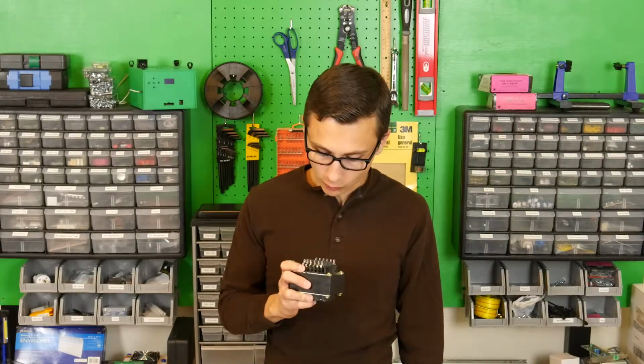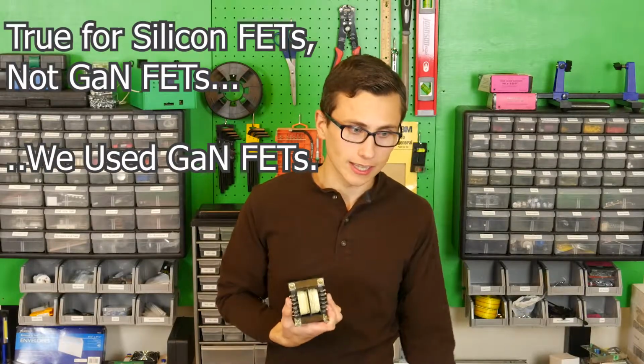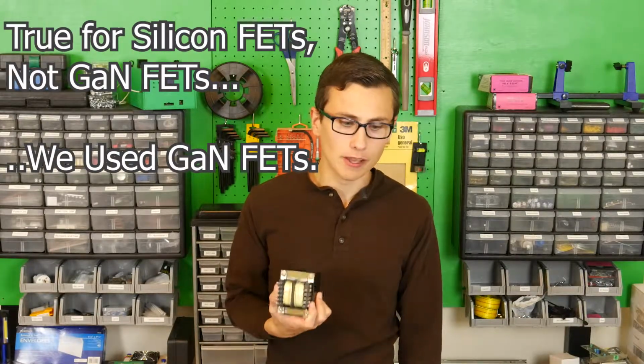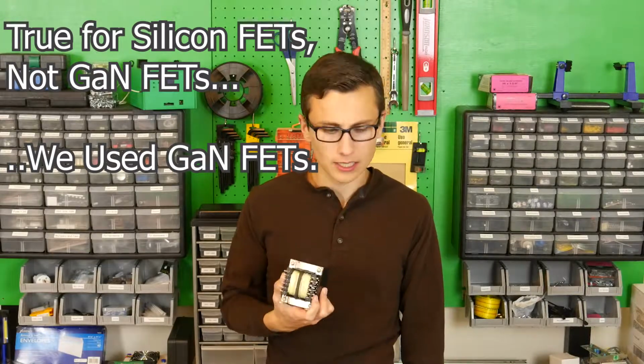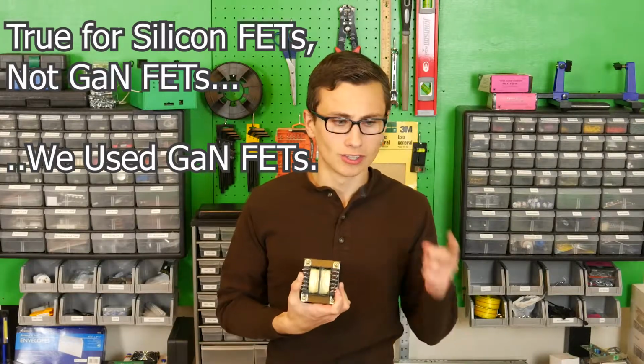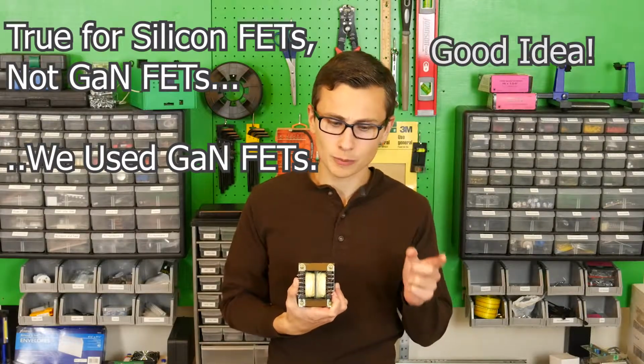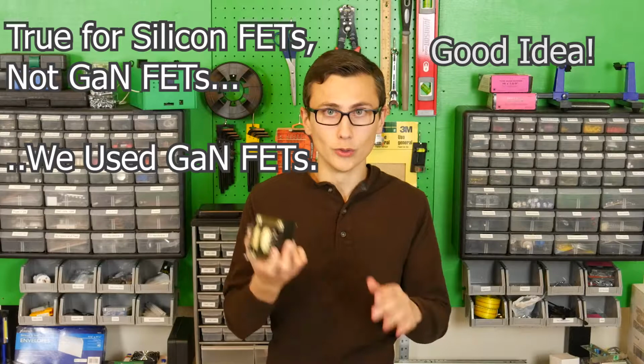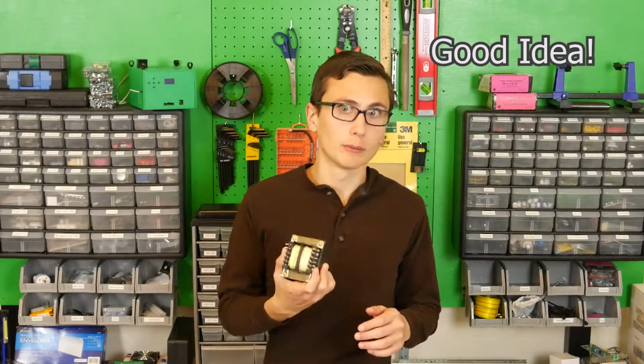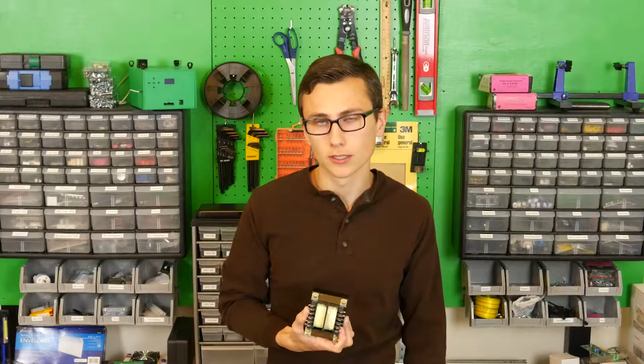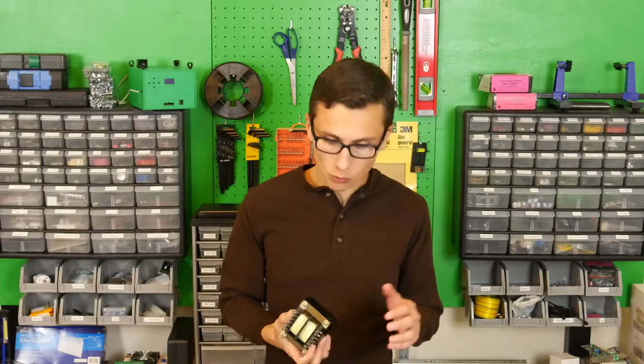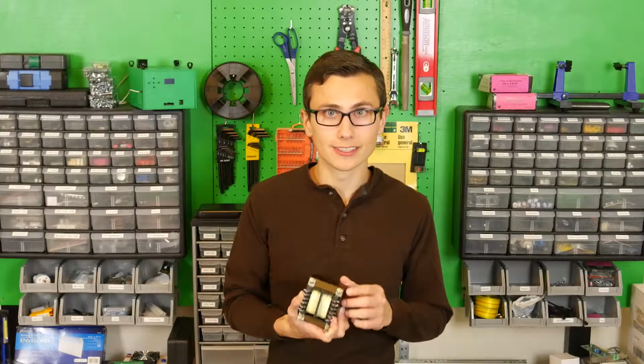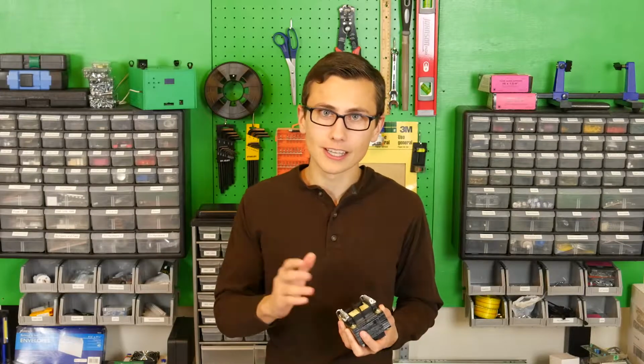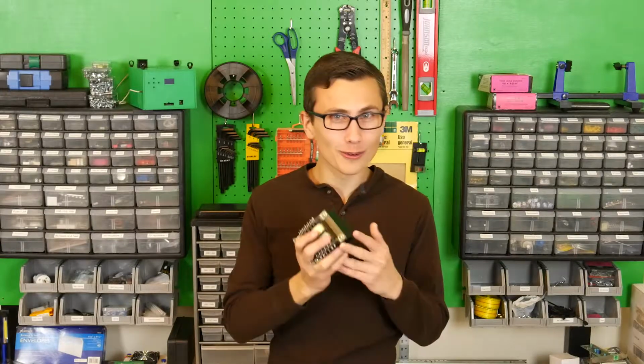It couldn't have gone above 40 volts, that's our DC bus voltage. It would have been clamped if it went above that. I should add clamping diodes to limit it to the DC bus voltage, since that should be higher than anything we see on the output, so we know our transformer can be rated for it. We should blow up those diodes before we blow up a transformer. These things aren't cheap. Well, this one was, but in our final design it'll be a 1500, 2000, maybe 2500 VA transformer, and those cost like $300. I don't want to overvolt them and short them out.